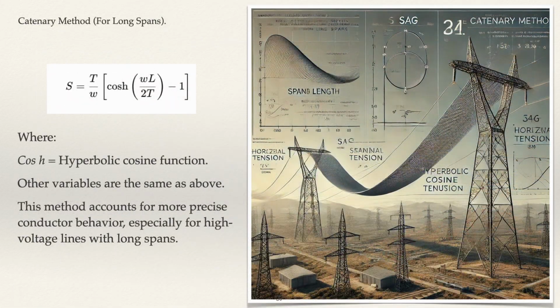2. Catenary method for long spans. For longer spans, the conductor forms a catenary curve and the calculation becomes more complex. The sag S is given by the formula, where cosh equals the hyperbolic cosine function. Other variables are the same as above. This method accounts for more precise conductor behavior, especially for high voltage lines with long spans.